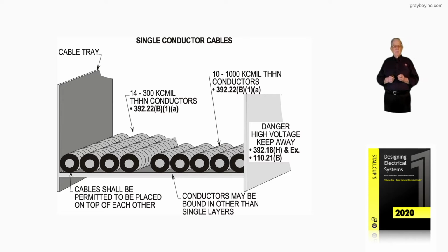392.22(B)(1)(a). And then notice these cables shall be permitted to be placed on top of each other, and more especially where they're bundled together to provide even dividing of the current on each cable, if they happen to be L1, L2, and neutral, and that kind of thing. Now, to the right, we have 10 1,000 kcmil THHN conductors.